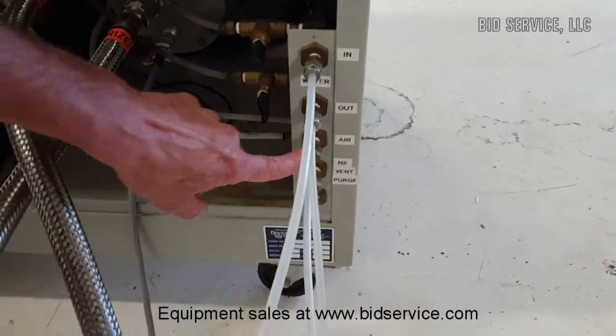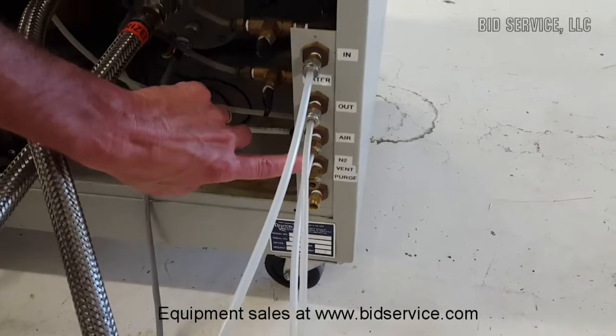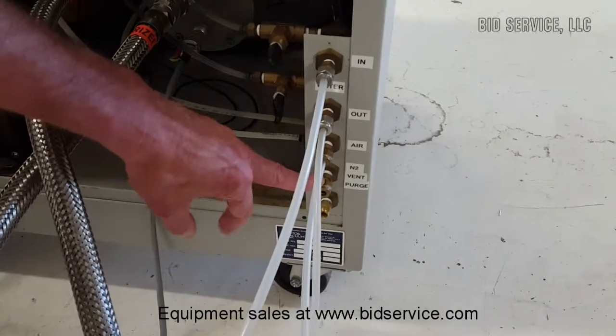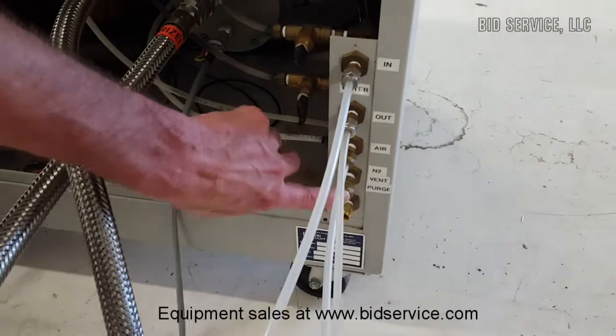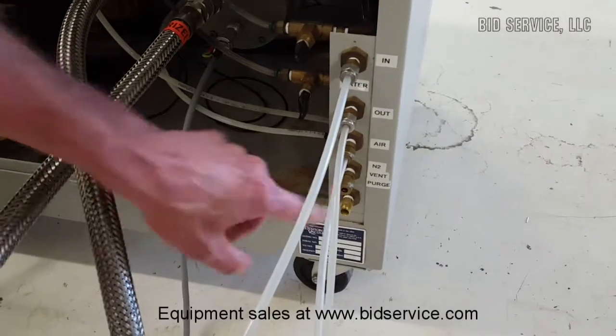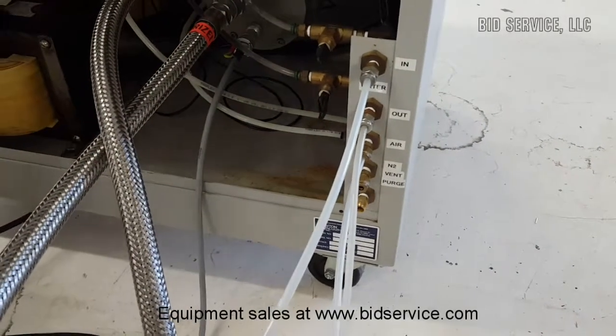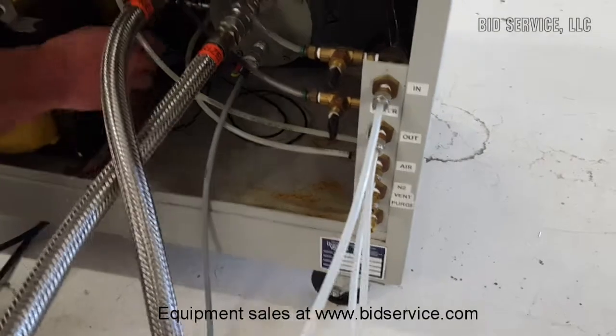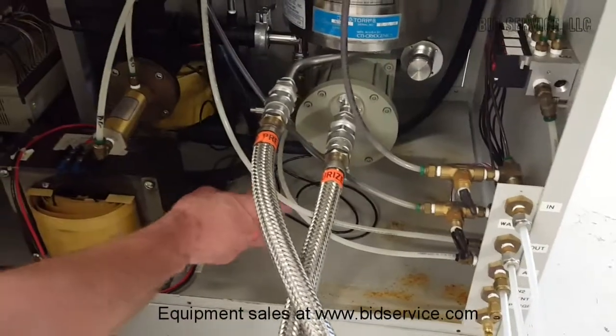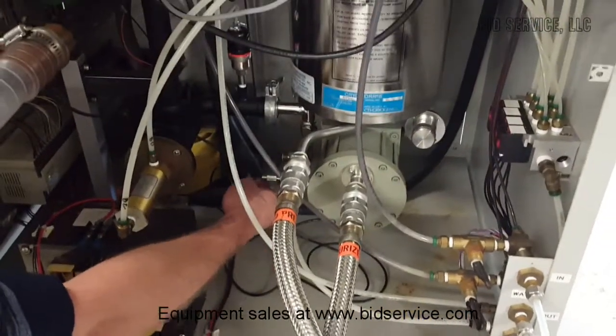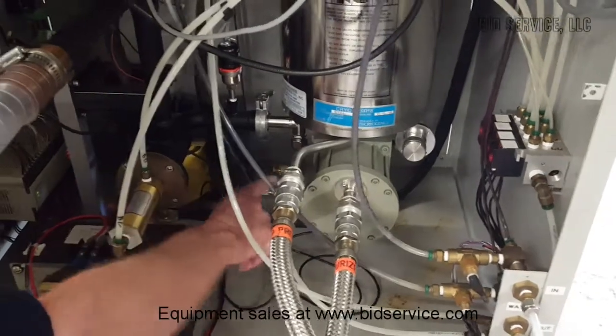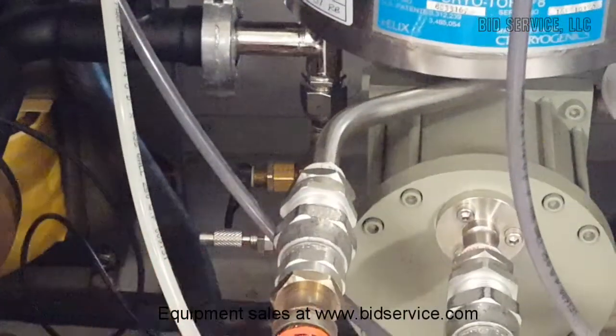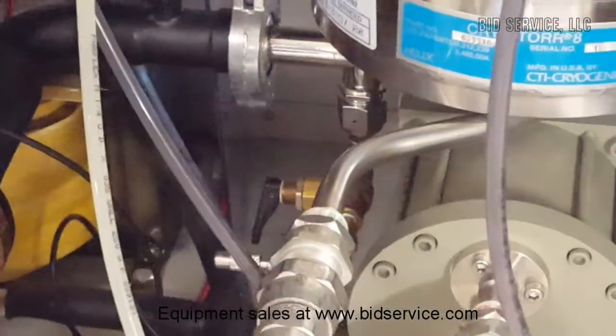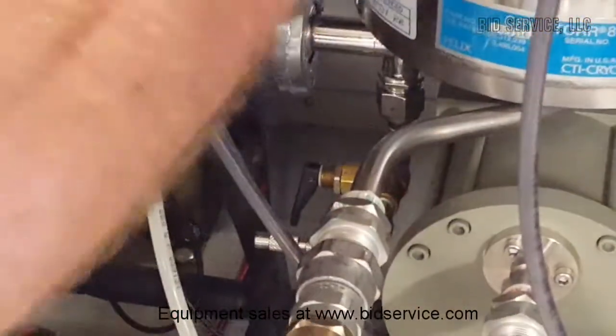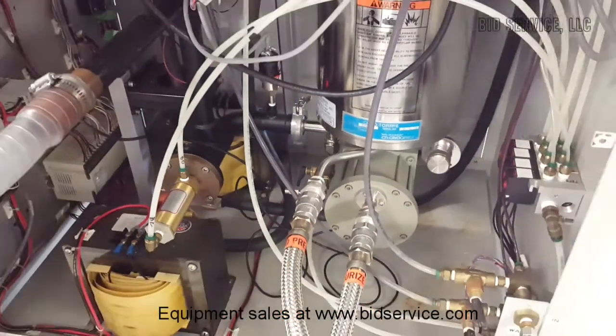We have an air line, and that's to operate some of the valves, the pneumatic valves. And then here you would hook up your nitrogen for venting and for doing the regeneration. When you go to do a regeneration, you're going to have to manually shut the cryo compressor off and then open this valve here, a little needle type valve, and that'll allow the nitrogen to go in and warm up your cryo pump.